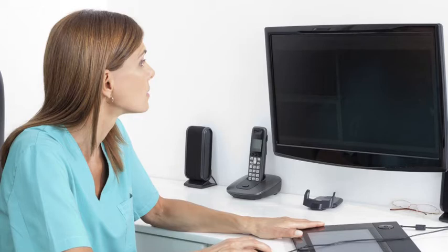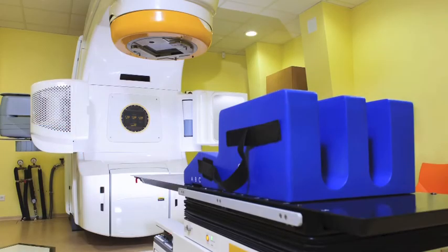A therapist must leave the room during the treatment and rely on the shielding built into the structure of the treatment room for protection. Depending on the strength of the X-ray beam being used, the thickness of the walls of a radiation therapy treatment room often exceed 3 feet of solid concrete. The thickness of the wall can be reduced if materials of higher density are used, such as lead.